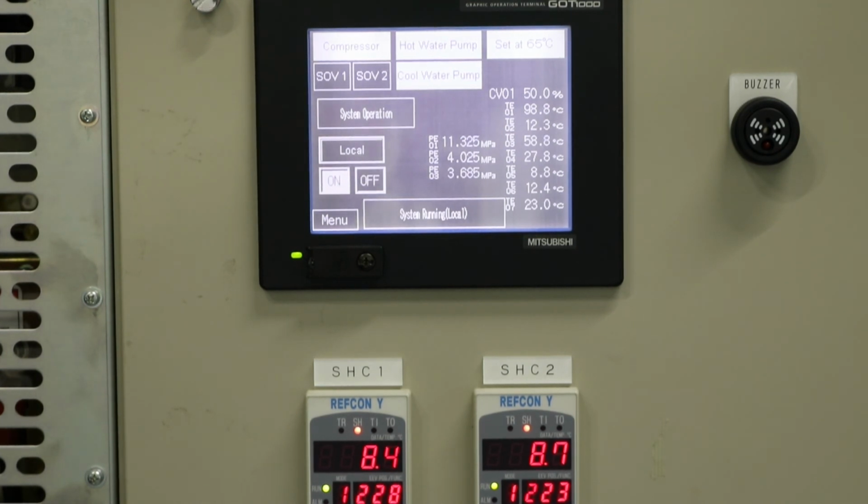These are the temperatures of the upper source. So the water of the upper source comes in at the temperature 27.7 degrees Celsius, and it's heated up to 59.6 right now. And we use this high temperature water to heat up our building.